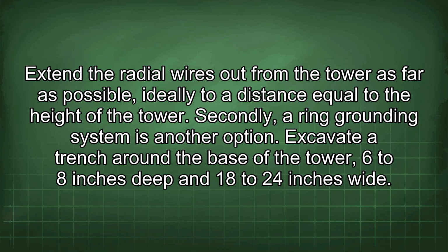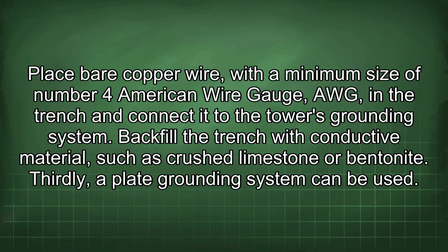Secondly, a ring grounding system is another option. Excavate a trench around the base of the tower, 6 to 8 inches deep and 18 to 24 inches wide. Place bare copper wire, with a minimum size of number 4 American wire gauge, AWG, in the trench and connect it to the tower's grounding system. Backfill the trench with conductive material such as crushed limestone or bentonite.